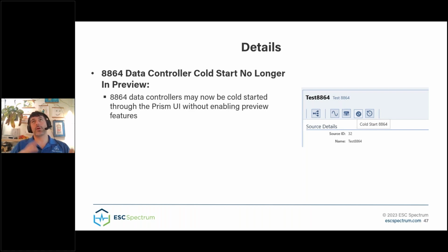It's basically a factory reset. And then once it comes back online, it will download all the channels, all the digitals, all the calibration sequences, and the Modbus server.cfg thing. So essentially, it's meant to be an easy button to set up your 8864. Like, let's say you had to swap one out, for example. Like something blew up. You could plug it in, just hit the button, and it should program your 8864 for you and get you back up to speed.